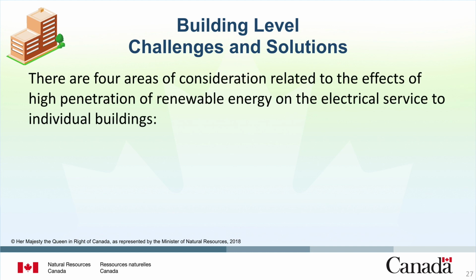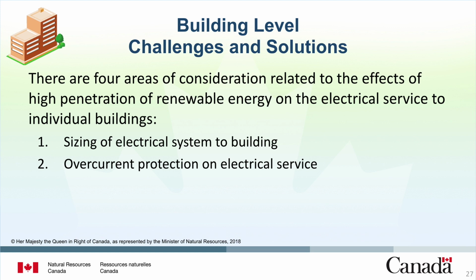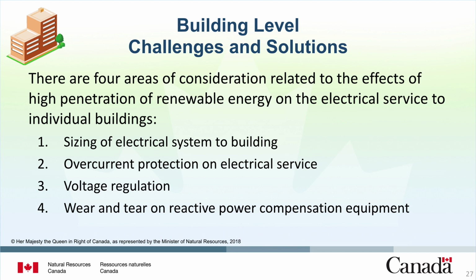Let's begin by focusing on the challenges and solutions at the building level. There are 4 areas of consideration related to the effects of high penetration of renewable energy on the electrical service to individual buildings. 1. Sizing of electrical system to the building. 2. Overcurrent protection on electrical service. 3. Voltage regulation. And 4. Wear and tear on reactive power compensation equipment.